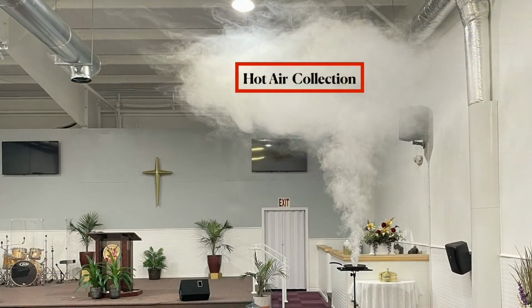So you can see here, we light off a smoke bomb, watch the smoke patterns. So this is from the height of a seated adult here, the smoke bomb. You can see the air is rising, there's no mixing going on. So if someone was sitting next to this person, right here, someone was sitting next to this guy, and on the other side of this person, you can see they will not be breathing this person's germs, because this person's germs are going up in the air with the hot air.